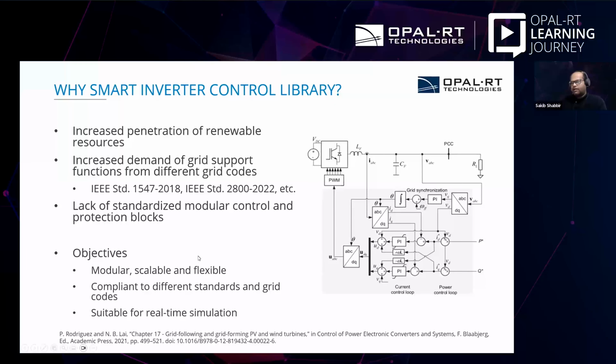In addition, the protection functions integrated in the smart inverter library are configurable. Although the library was particularly developed for IEEE 1547, based on these configurable characteristics, the blocks can be applied to any grid standard. Users can modify them depending on their need. Most importantly, all these toolboxes have been developed to reduce the computational burden, so that we can easily implement them in real-time simulations.